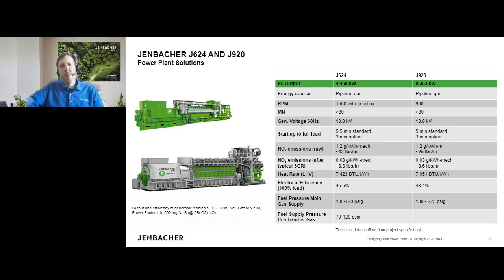If I were to contrast these engines, the 920, due to its higher efficiency and higher power output, might be an engine to use for very large plants in the 100 megawatt space. Also, those plants which would be base load, where you have advantages from using the higher efficiency engine. The J624 is a more flexible option for smaller plants, somewhere around 10 to 60 or 70 megawatts, and also for peaking plants, because these high-speed engines specifically offer a lower cost on a per kW basis than a medium-speed engine. So they have a very attractive capital cost, while still maintaining very good outputs and performance. These would be very well suited for smaller peaking plants.